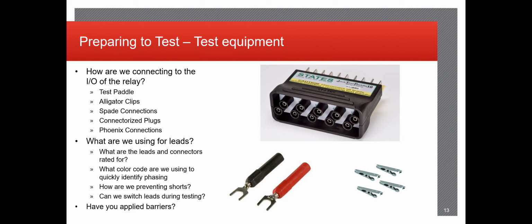Barriers are extremely important. Those are pretty much any signage, caution tape, anything like that. You want to designate the area that you're going to be working in, because the test set you're going to be utilizing is going to be pushing DC voltages and currents and AC currents and voltages pretty much as long as you're testing. So you want to make sure that everyone knows that the area is marked off so that they don't unintentionally mess with the set and possibly injure themselves or damage equipment.